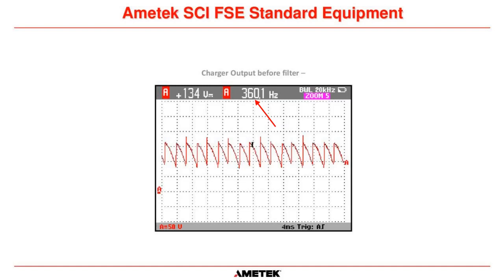Now, if there was a pulse missing here, for example, because let's say the gate lead to one of the SCRs had come loose and one of the SCRs wasn't firing, the charger would actually still work. Our chargers will still work with one SCR taken out of circuit as long as it's an open circuit. And you're not really going to see the detrimental effects of that until you put full load on the UPS, which is very rare, or after you've done a battery capacity test and you're putting the batteries back on charge. So it's extremely important we see that.